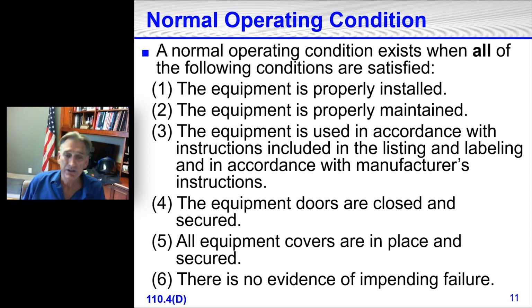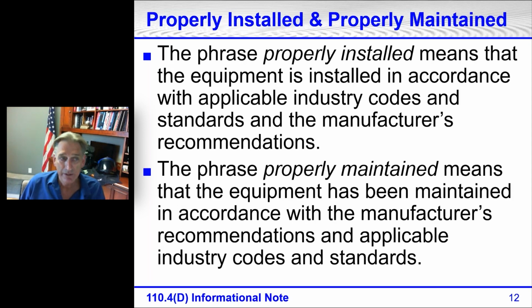Number 6, there is no evidence of impending failure. This is a big one. We'll talk about that in a couple of slides from now. Let's talk about the first couple of them. The phrase properly installed means that the equipment is installed in accordance with applicable industry codes and standards and the manufacturer's instructions. Again, it has to be read and properly installed. It would have to be installed in accordance with the National Electrical Code, as a good example.